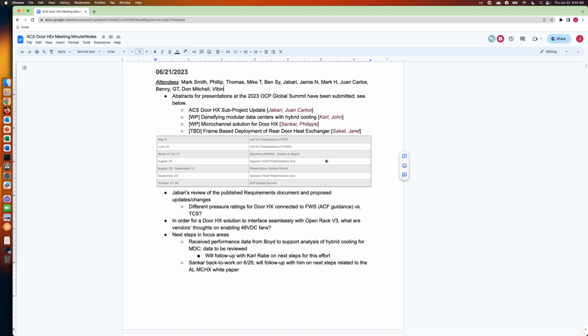Maybe also the quick couplings, the blind mate couplings, have too much to say, because if you want to connect it, you have to bring pressure or force against the pressure in the system. This is really high, it's really high. More power, more flow rate, and more pressure will mean more force, because the surface of the quick couplings will be bigger. So I don't think it makes sense to increase the pressure in the secondary loop to 10 bars. Okay, we can do that, but no one will do that. Yeah, there's no way it'll pass with 10 bars, that's for sure. Something in that loop will fail before that.